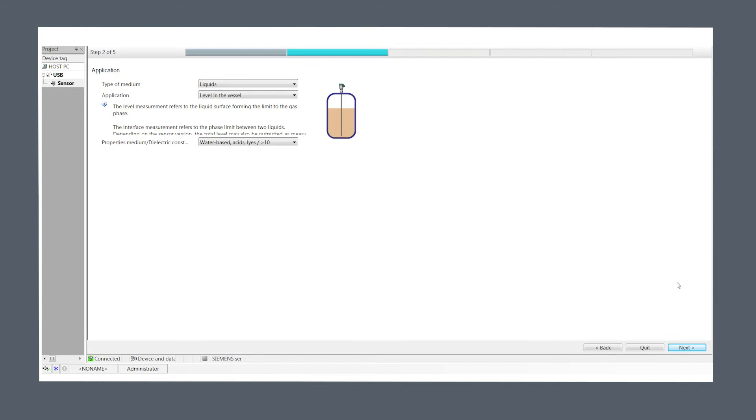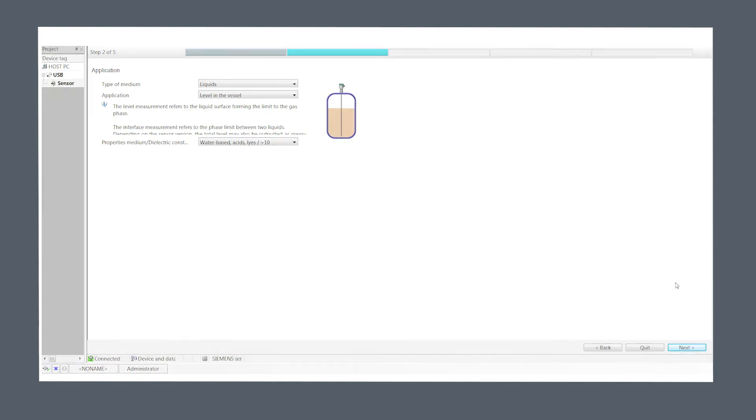Step two, application. Select as appropriate for your application. In this example, we have selected level in vessel for our application and water-based acid with greater than 10 dielectric as medium properties.